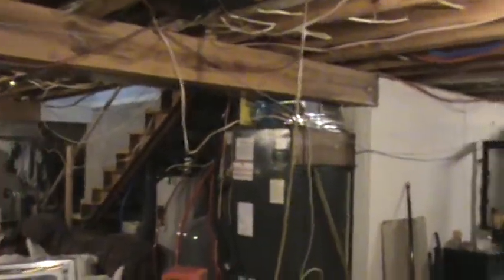I'll show you one more thing before I let you go. You can kind of see a little better the second set of ductwork. There's one set of ductwork coming off the top, because remember, air flows upward through this unit. So here's the ductwork that goes back and services the bedrooms and back of the home. Here's the ductwork that goes up. It actually jogs over just a little bit and then goes forward in here behind this concrete wall. And then of course it branches off there, and there's another one down farther you can't see. Similarly on the other side of the home. So the main trunk is really this back one here that's supplying heat to go forward into the home, because that's the bigger area of the home. And this is smaller. The duct size is the same, but the ductwork coming off of this main supply here is a lot smaller than these are, because there's less area in the back of the home.